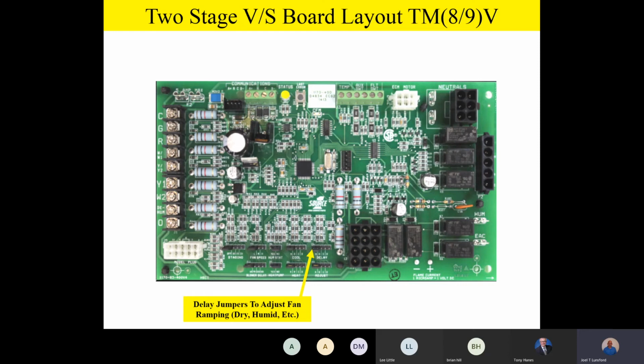Because remember, team, just some of the basic physics of the air conditioning and refrigeration cycle, the colder the evaporator, the more moisture you're going to remove from the air going over it over a period of time. So we're going to utilize that science with this delay jumper. So in the humid profile, we start the fan out at 50% airflow, then we ramp it up to about 82%, and then we ramp it on up. So we have this stepped airflow to help really pull extra moisture out in the cooling mode of operation.